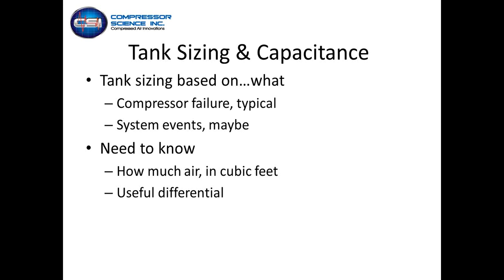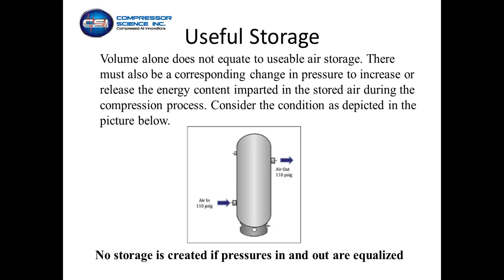So, tank sizing and capacitance: what are you putting in a receiver tank for? I have customers that say, I'm putting in a receiver so that I have storage. Well, just putting in a receiver doesn't necessarily mean that you have storage in the building. It means that if you have the same pressure in, it's the same pressure out. Basically, there's no storage going on. You've basically got a bulge in the pipe. So it will allow compressor controls to slow down and respond a little bit, but generally when you have a rapidly moving system that's using all the flow you're giving it, pressure in, pressure out, it's just going right through the receiver tank.